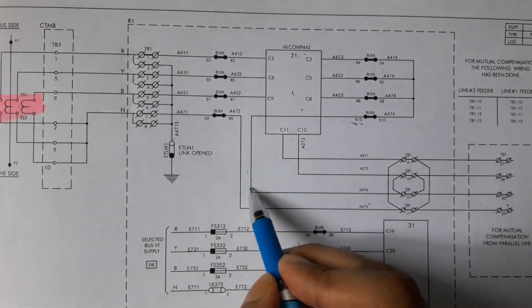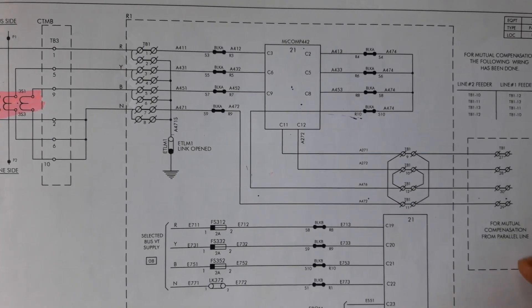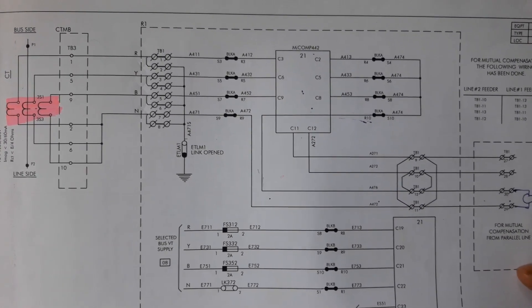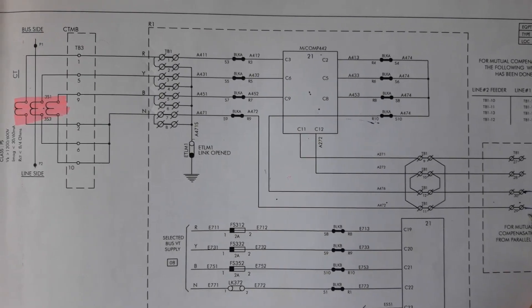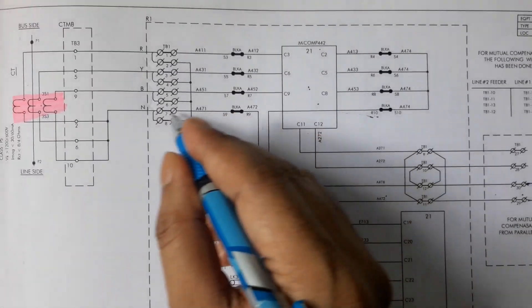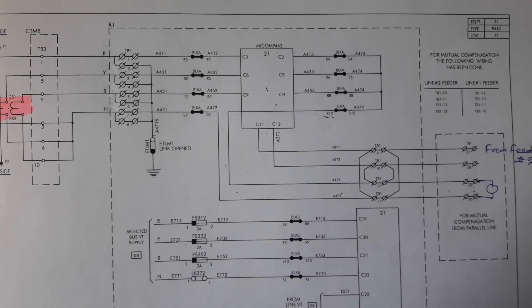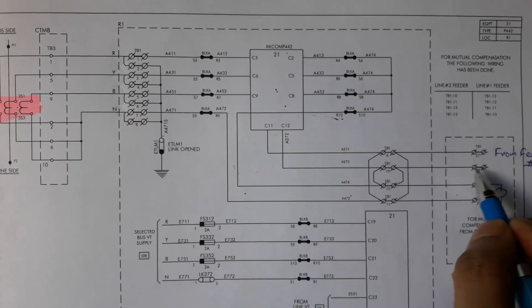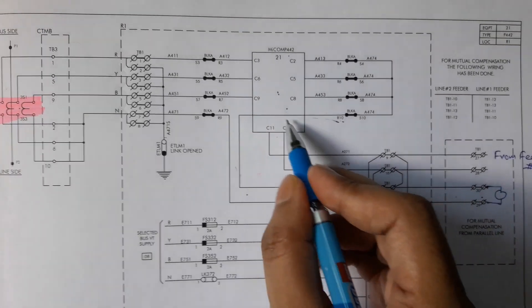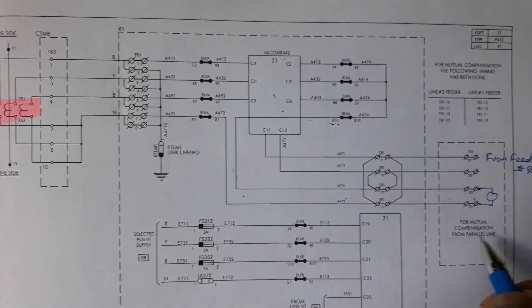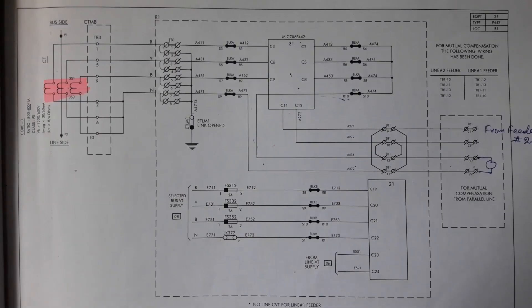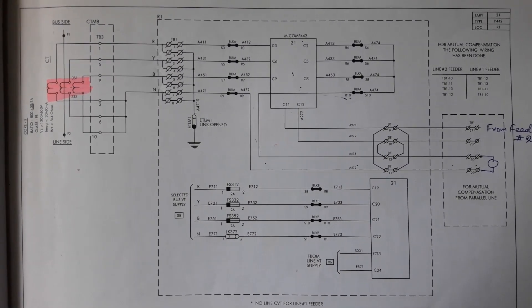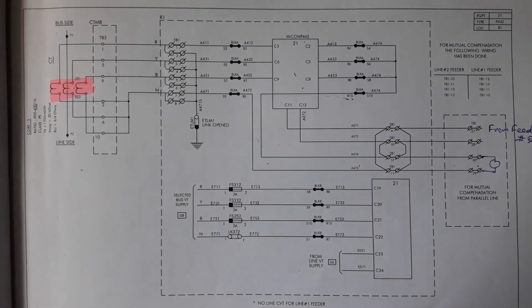The neutral connection of feeder 1 will go to feeder 2, pass through its mutual compensating coil, and return to feeder 1. Similarly, the neutral connection of feeder 2 goes to feeder 1 and passes through its mutual compensating coil. If a parallel circuit is not present, mutual compensation is not required.